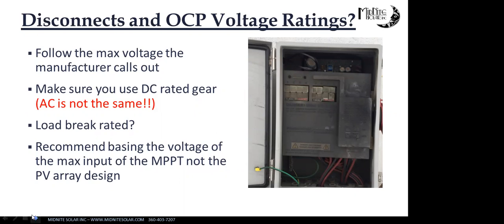And then the last point I want to make is following the voltage of the system. How do you pick your parts? Let's say you're going to do a PV array that's 100 volts VOC, and you're going to do a Classic 150. That's kind of a poor example, actually. No, it still works. Let's say you do the PV array of 100 volts, you do a Classic 150, and you say, I'm going to put an SPD 115 on that because it's 115 volts. The array is 100 volts. And it works perfectly, right? But the problem is that if somebody else comes behind you and puts one more module in series, they've exceeded that 115 volts.